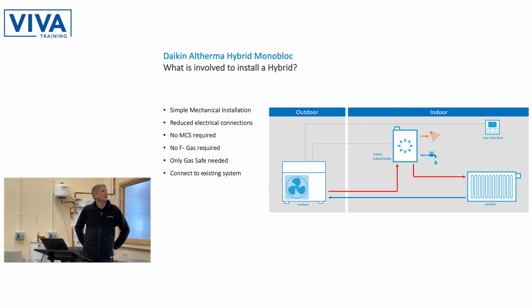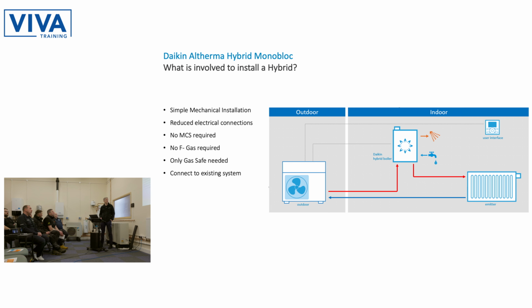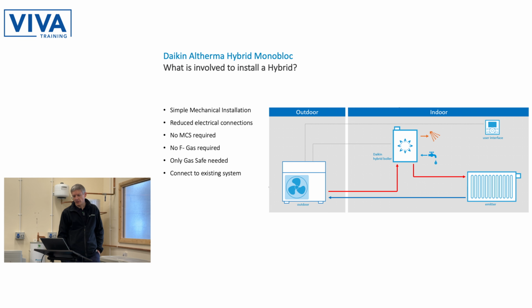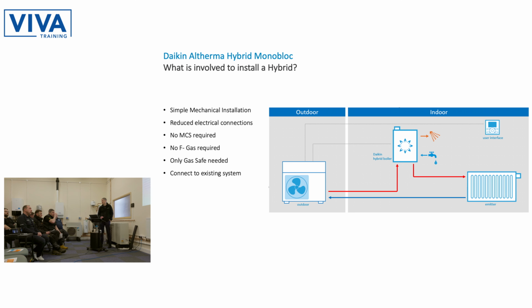So what's involved in installing one of these? It's a pretty simple concept here. So we've got the heat pump. That goes outside. So that white line there is differentiating the wall between inside and outside. The warmed water flowing from the heat pump flows into the combi boiler, which is inside. The water pump is in the boiler, so there's no additional pump to install. That will pump the warmed water, boost the temperature if necessary, around the heating system, and rather than returning back through the boiler, the return from the heating system goes straight back into the heat pump. So, 3 points of a triangle in terms of the installation setup.